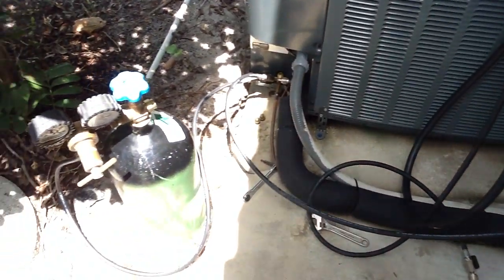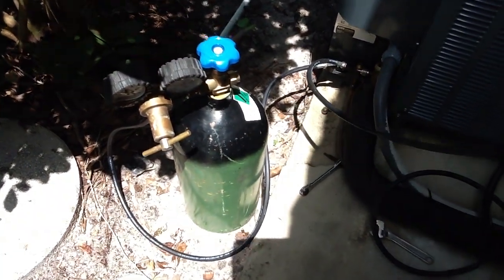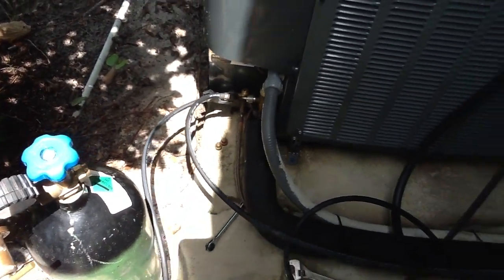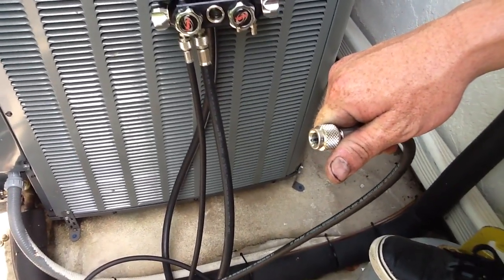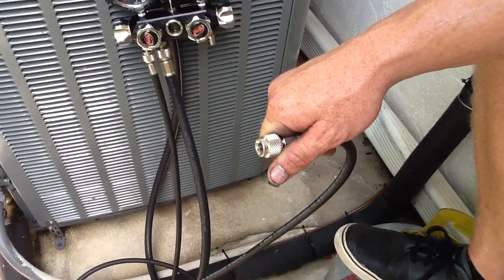To summarize: you hook up your nitrogen tank to the suction or liquid side, then crack open the other hose so you can just barely feel the nitrogen coming out. This prevents your unit from oxidizing while you're sweating, because you're displacing the oxygen.